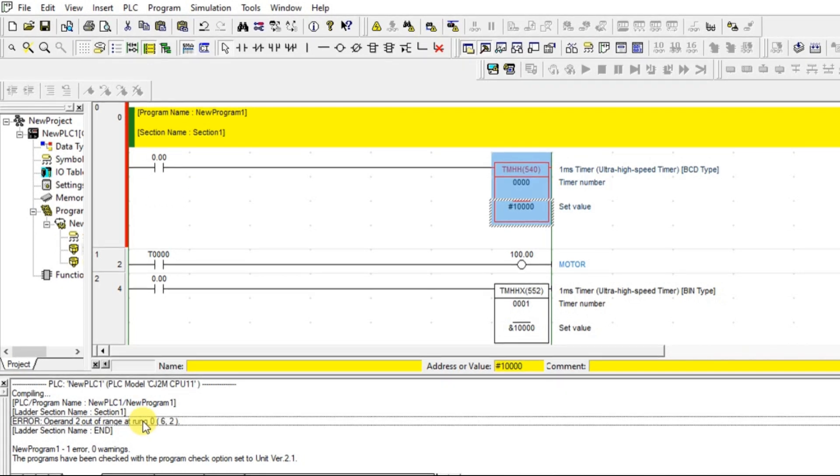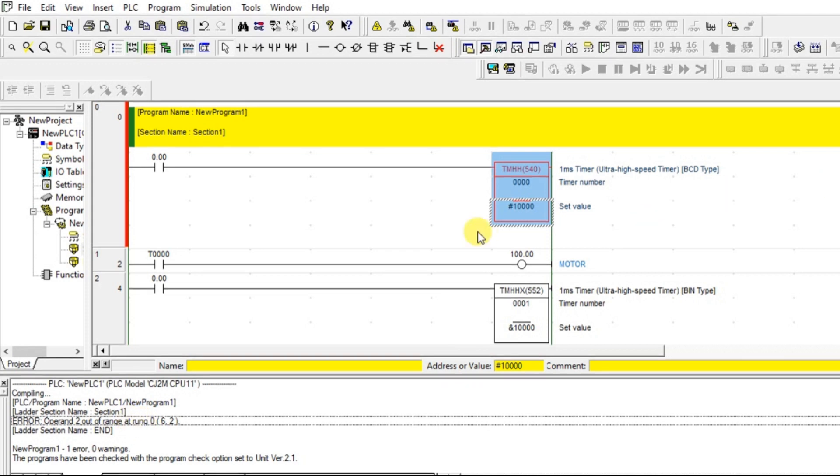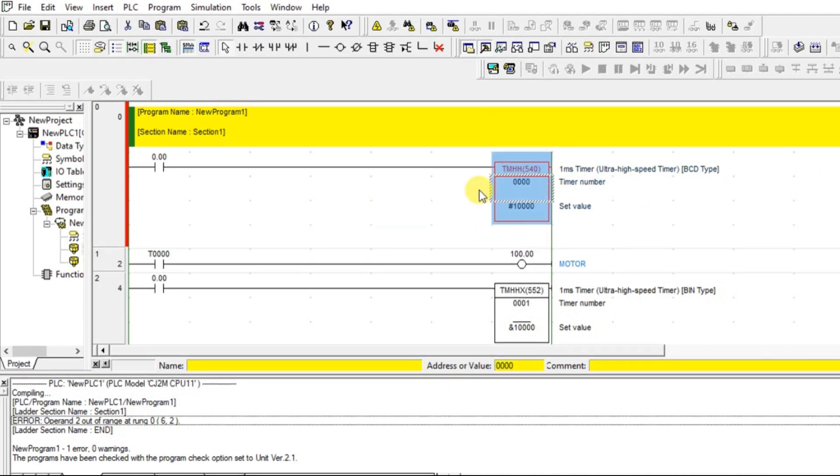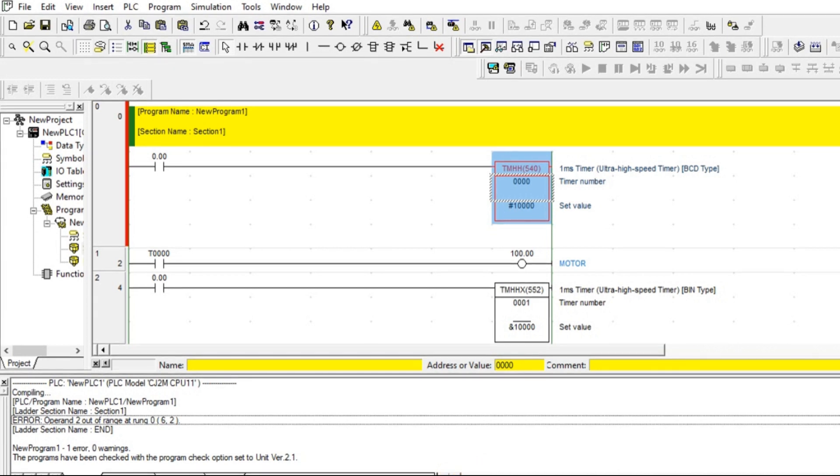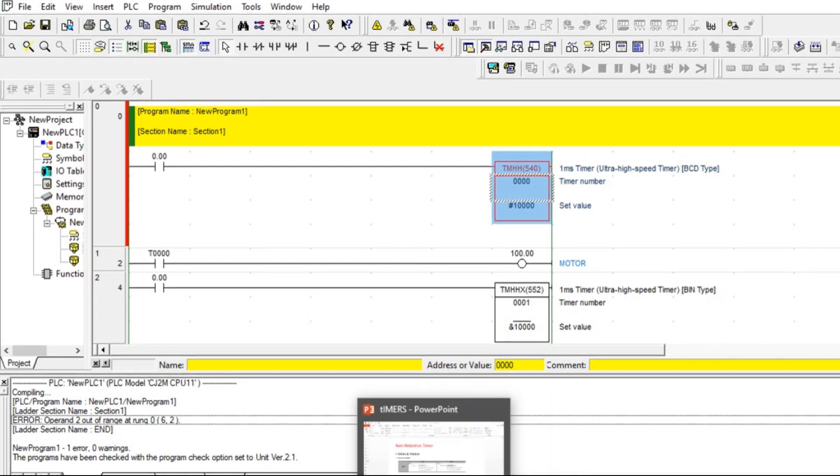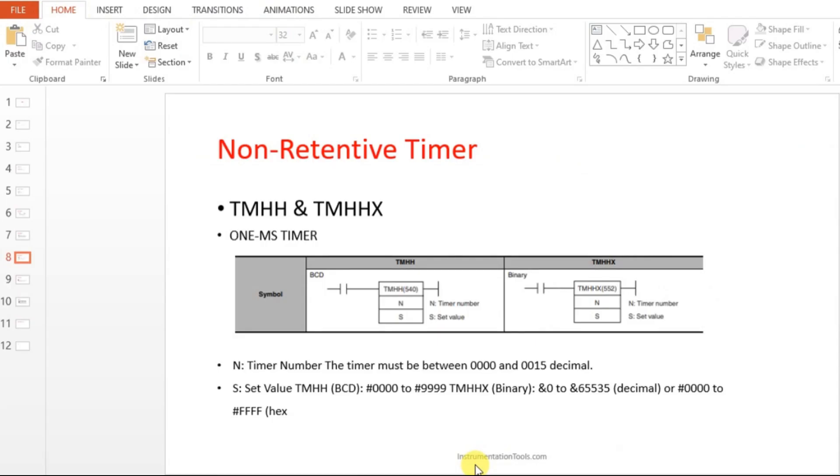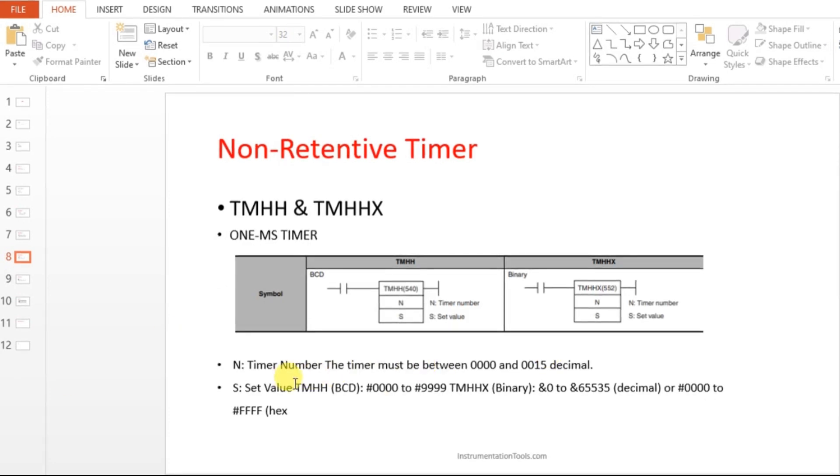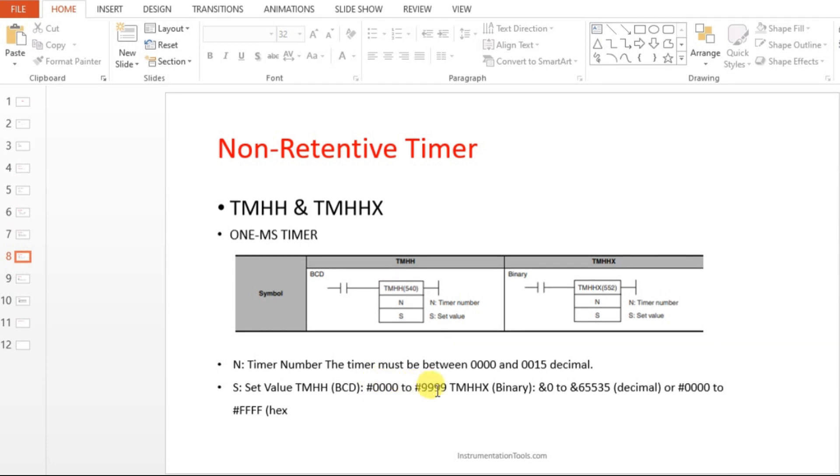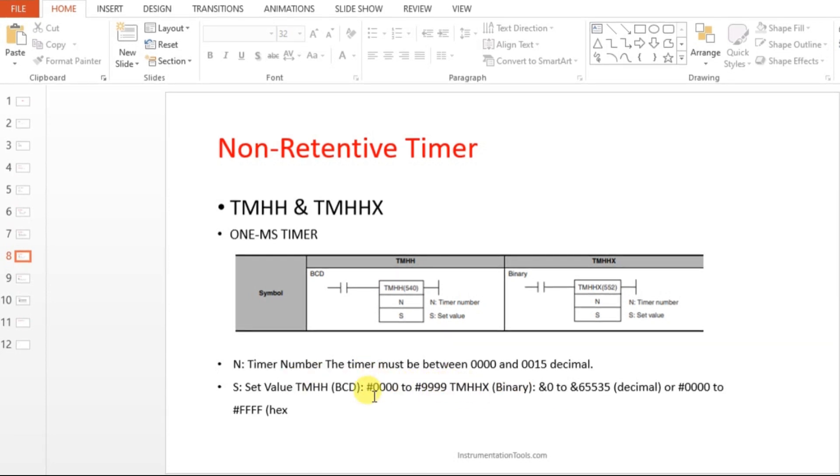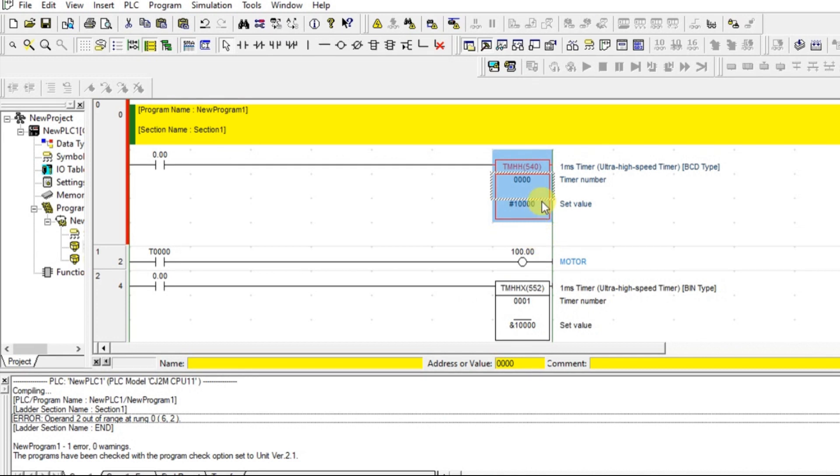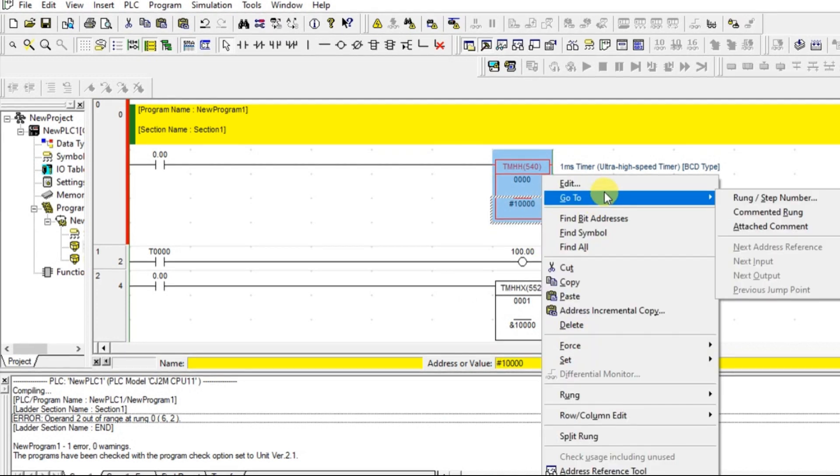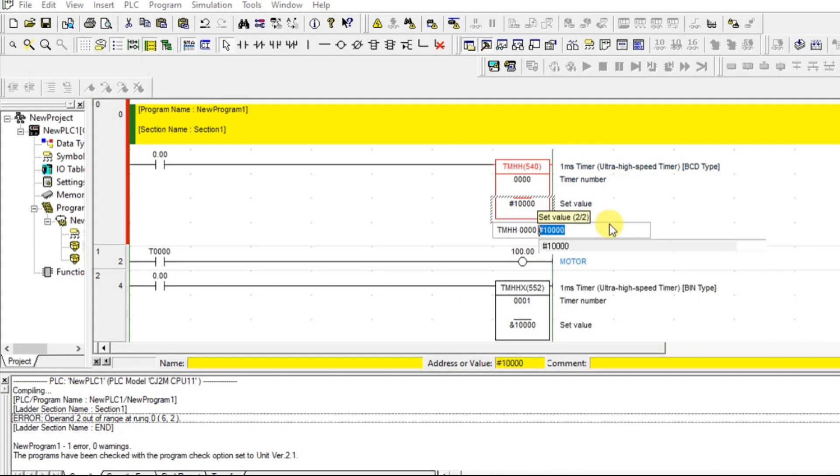Out of range. Okay, let's see what is the range we can do for this. Yeah. The range is 000 to 999. So that's what it is taking an error. So the set value have to be in range.